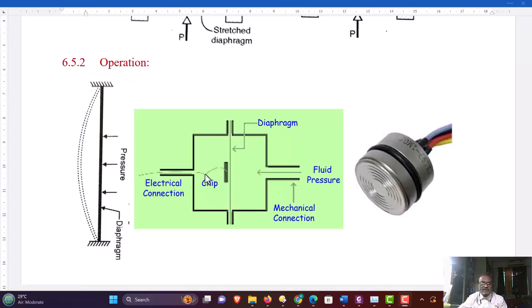If the detection element connected to the diaphragm is a strain gauge, then the output of the sensor is in the form of change in resistance. Further, you can connect a signal conditioning circuit, mostly in the form of a Wheatstone bridge, to convert this change in resistance to a proportional voltage. Here, the third figure shows how practical diaphragm sensors look. Here, you will see the corrugated diaphragm, which is a metallic diaphragm, mostly for high temperature application. The metallic diaphragms are used. The stainless steel diaphragms are quite common for corrosive applications.